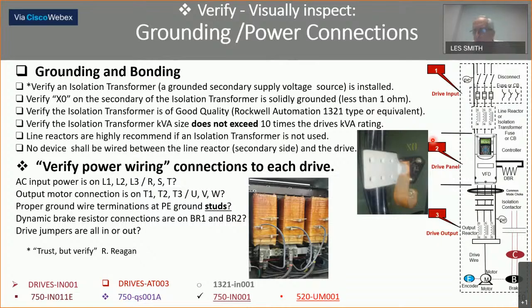Line reactors are highly recommended if transformers are not used, and they add the impedance up front on the drive. No device shall be wired between the reactor and the drive. This note was pulled through in that other document. You'll see a lot of these comments duplicated. Verify power wiring connections, just even checking L1, 2, and 3, making sure that they are wired directly from the power source, and then the T1, 2, and 3 are going to the motor. Yes, I have seen drives get wired backwards. Proper ground wire terminations go to the PE ground studs. Each drive will have one ground stud each, incoming power and outgoing power. They happen to be connected to the same bar, but symbolically it's nice to wire left on the in, right on the out wire. Drive jumpers should be all in or all out.